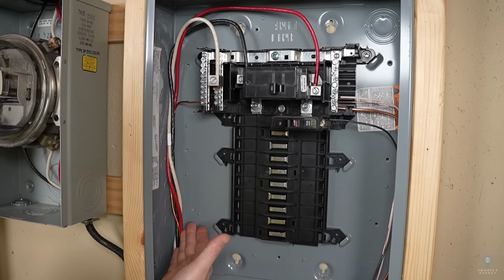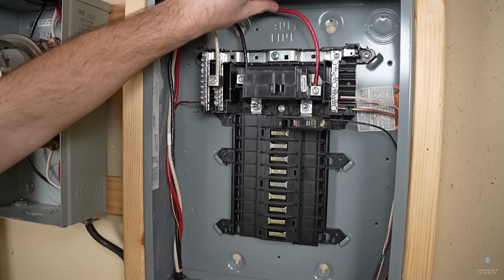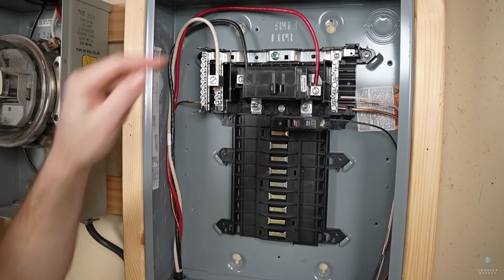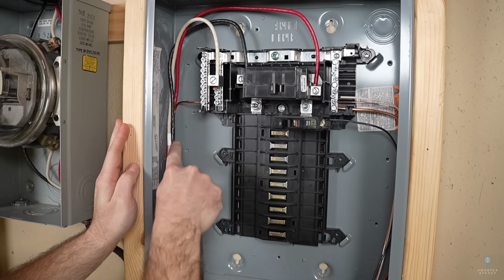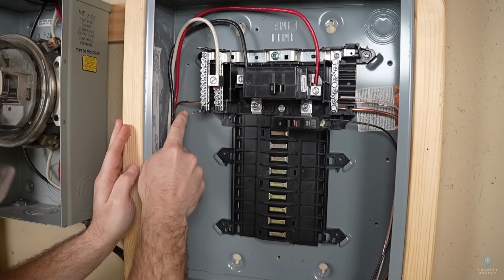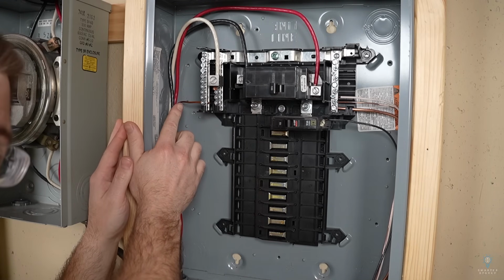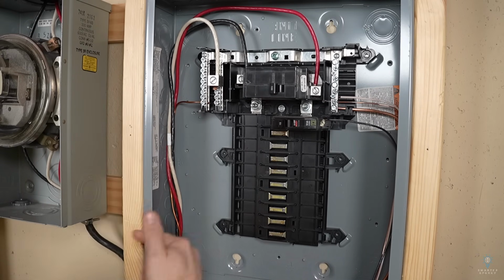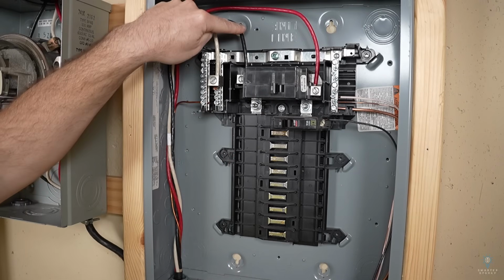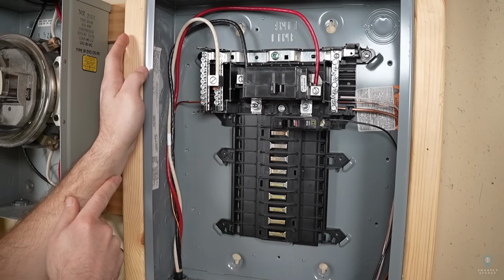So our service entrance conductors enter from either the meter socket or that emergency disconnect that you would have on a newer home, and they enter the panel. The two hot conductors land directly on the main circuit breaker, and the neutral lands on the neutral bar. Now, notice there is what appears to be a ground wire here. Now, this is not a ground wire in the conventional sense. We're gonna actually talk about this ground wire when we talk about the grounding and bonding section coming up. So for right now, let's just disregard this ground wire heading towards the meter socket. For right now, let's just focus on, we've got two hot conductors and a neutral, and they land on their specific locations in the panel.